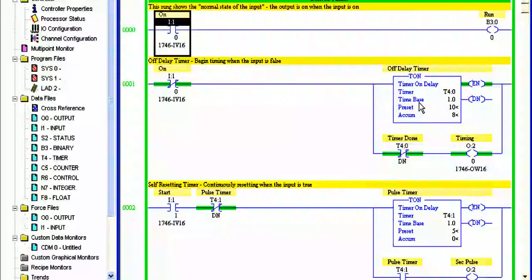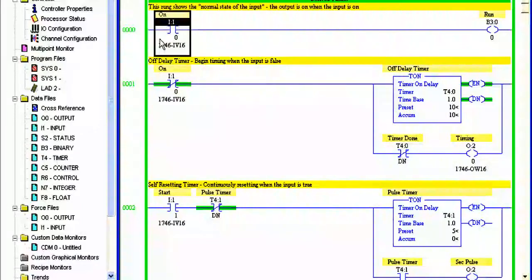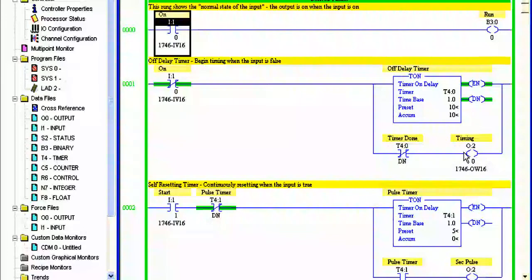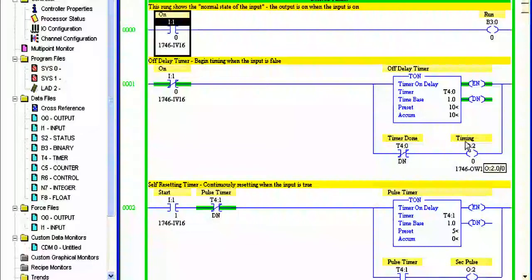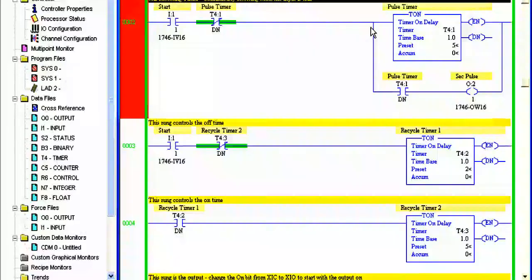And then it goes off. So that time period is time when it goes off. So just remember that I've turned the input off, it starts timing. Now you can actually have this either way. That doesn't have to be on, that can be, this could be an open contact, so therefore that timer could go on when the time period is finished. So that's a derived off delay timer.